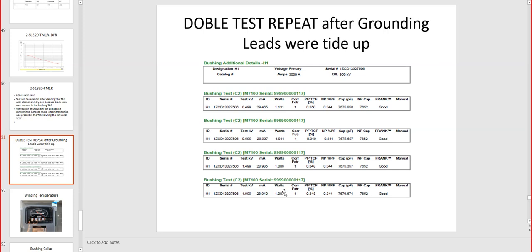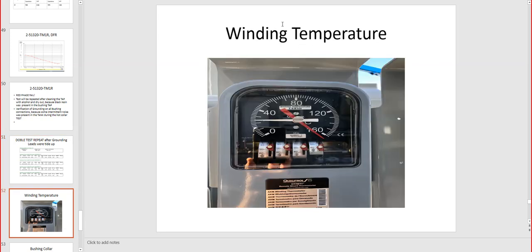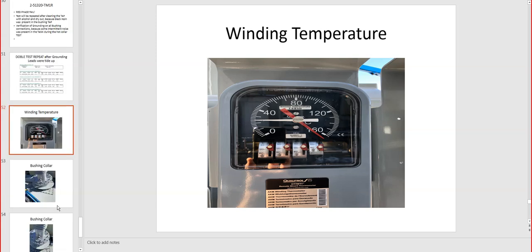You have the dissipation, the milliamp currents, 28 milliamps, is not dependent so much on the applied voltage, you can see. And then power factor 0.348 is pretty much stable. Then we have the capacitances in picofarads, the same, and it is declared as good. So basically we passed the test after corrections and the cleaning of the bushing. Winding temperature is just the instrumentation that is available on the transformer.